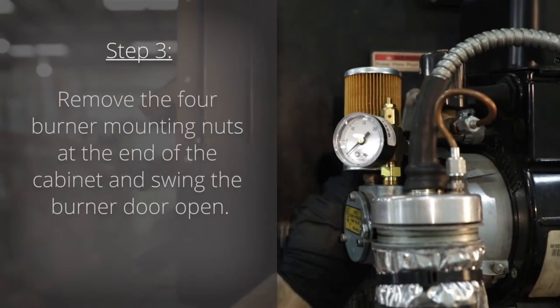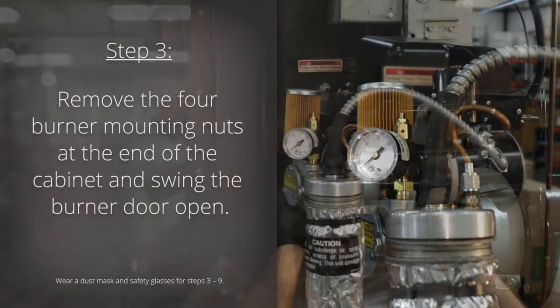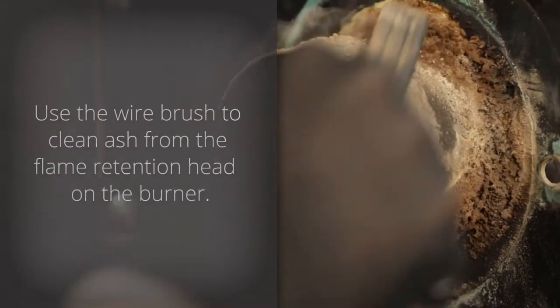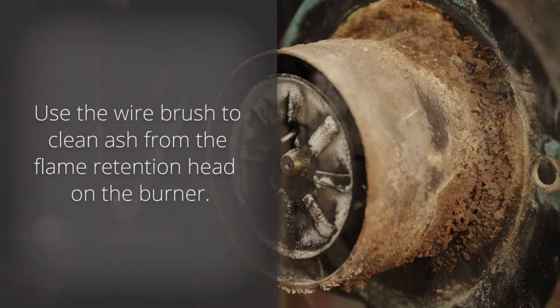Step three, remove the four burner mounting nuts at the end of the cabinet and swing the burner door open. Use the wire brush to clean ash from the flame retention head on the burner.